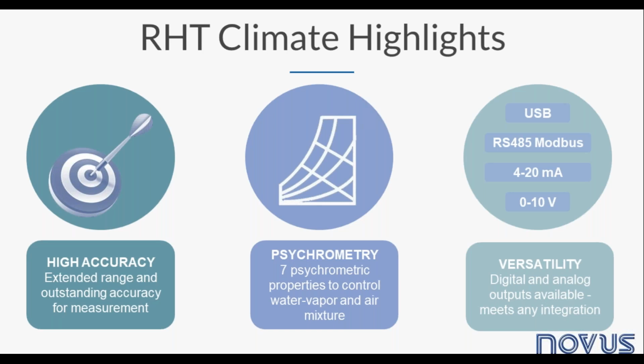The last highlight is the versatility of interface. It has a USB port for device configuration or commissioning. There is an optional RS485 Modbus protocol useful for integration with customer automation systems. The analog outputs are typically used as transmission signal for PLCs or dedicated controllers. So the Climate provides the ability to be applied in any customer project.